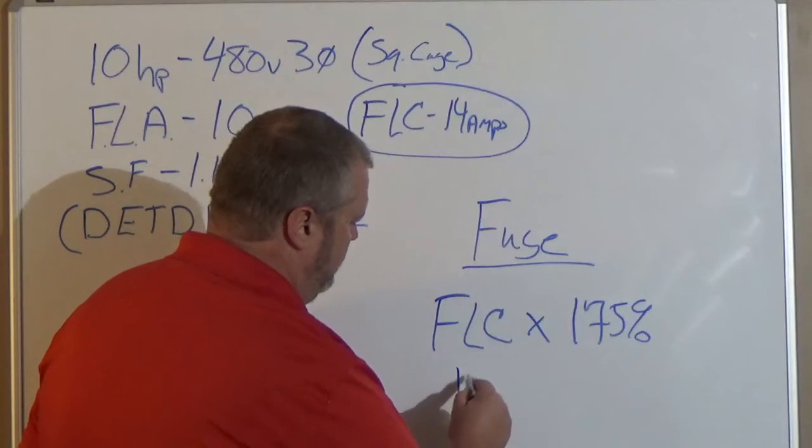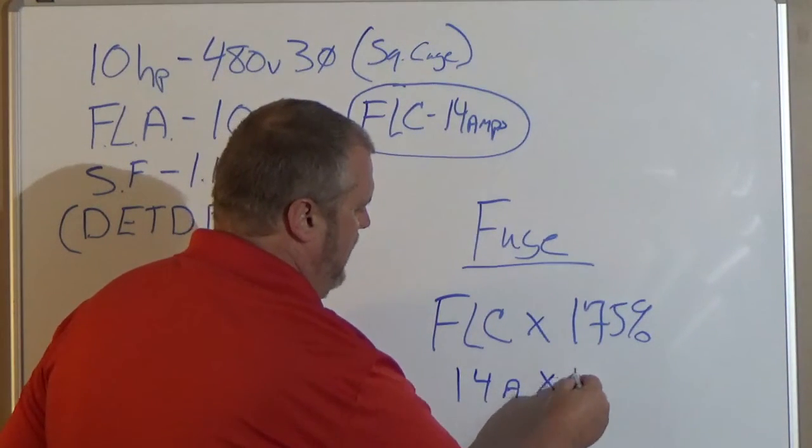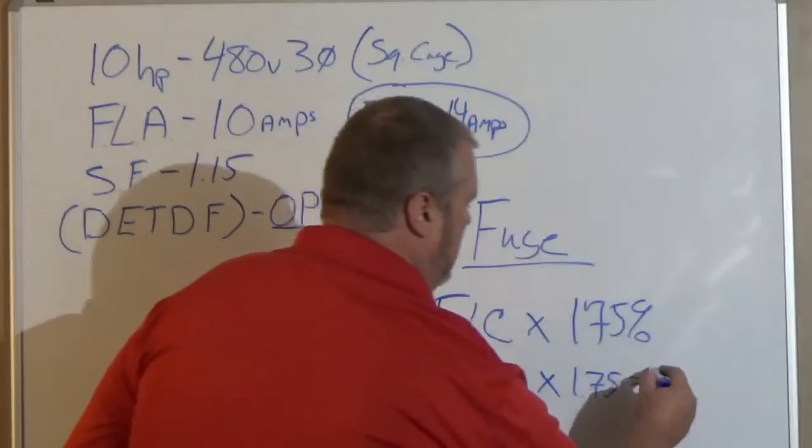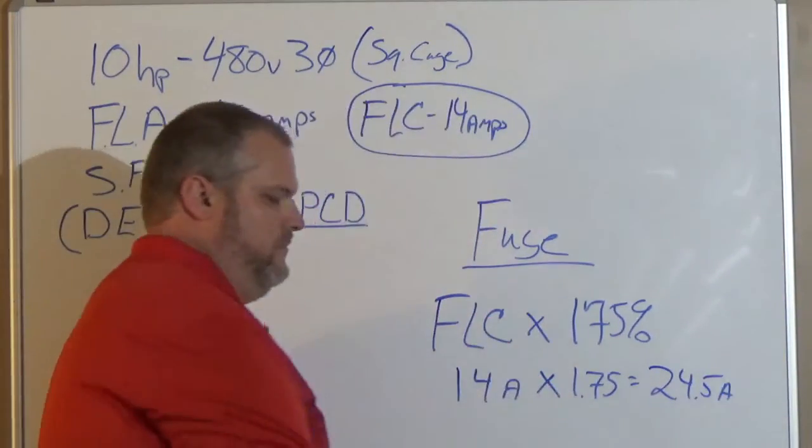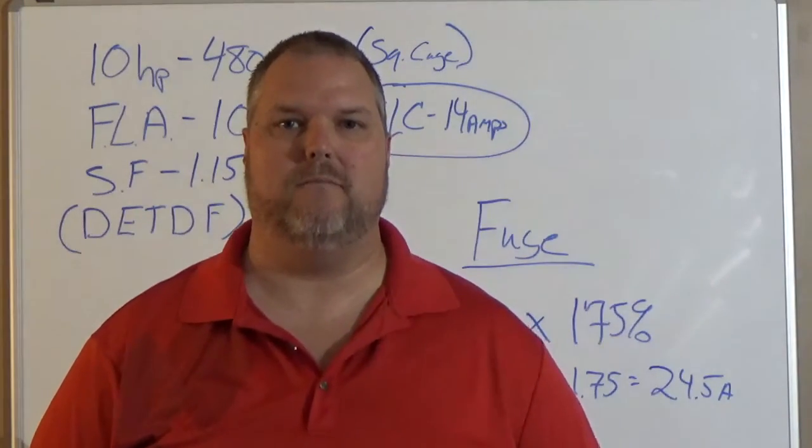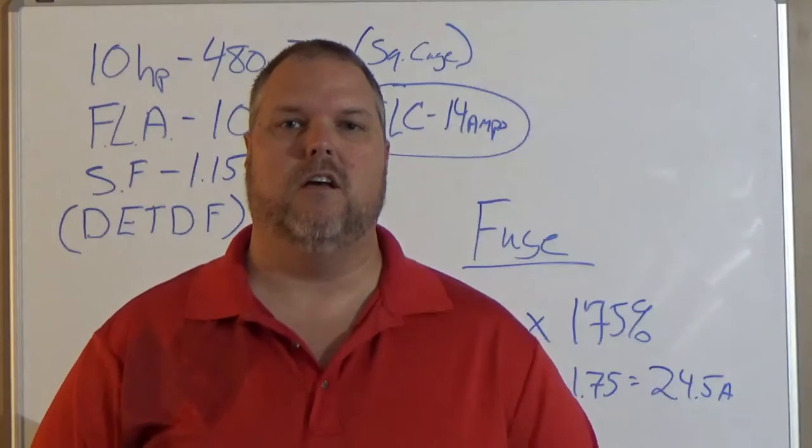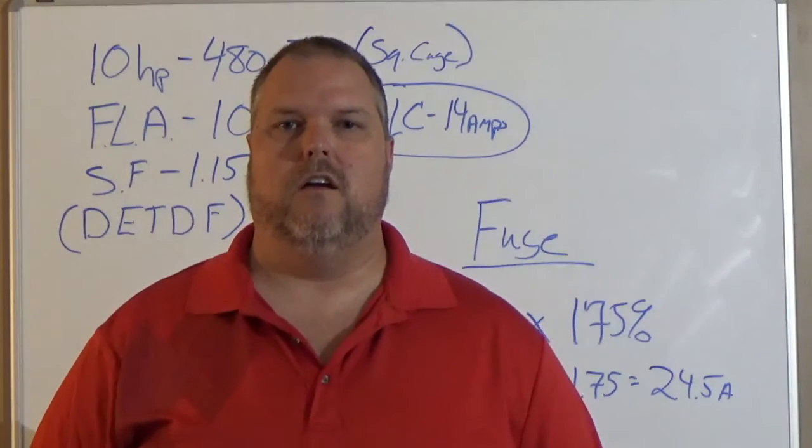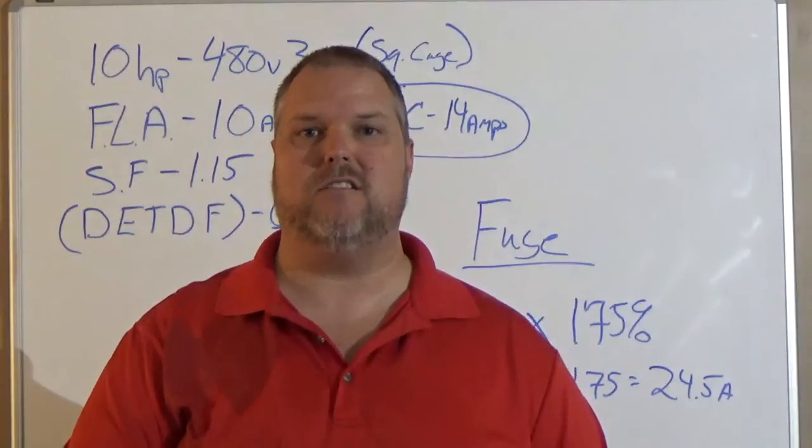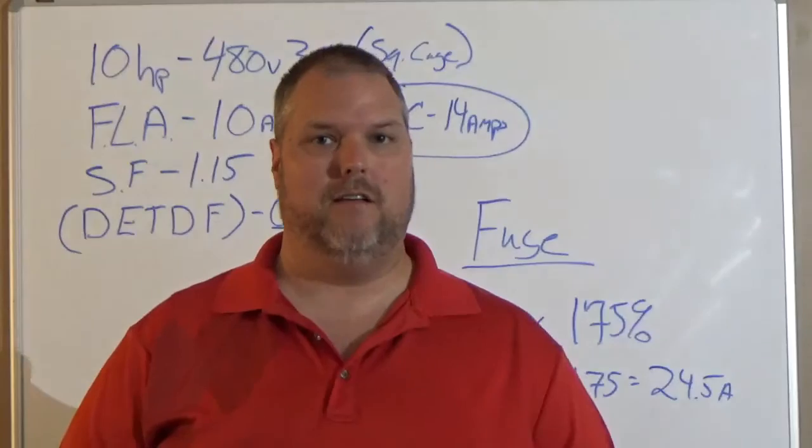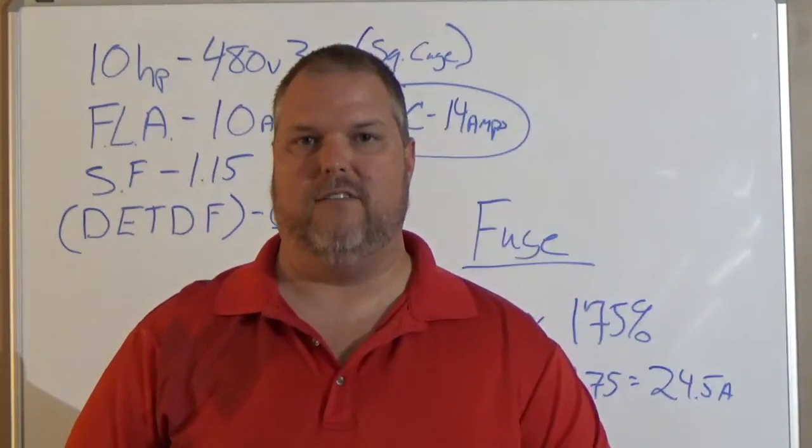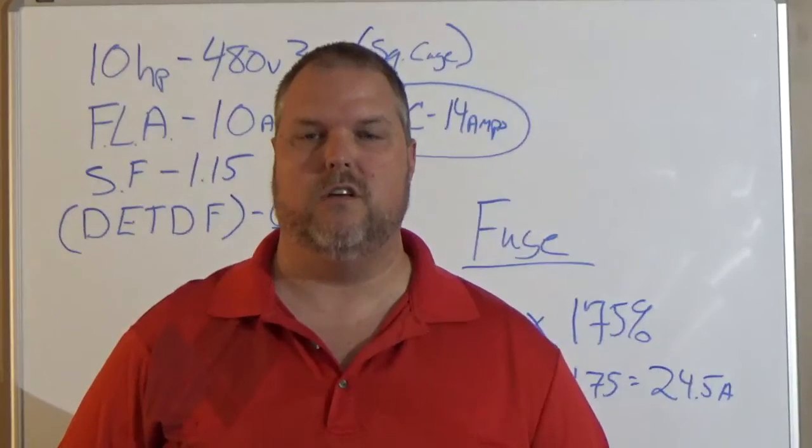Now, they don't make a breaker or a fuse that is 24.5 amps. So what we have to do is we have to go to the next available size. How do you find the next available size? Take yourself over in the code book to article 240.6. It's going to tell you that 25 is our next available size. We don't want to go back to 20 because we're looking at twenty-four and a half amps. That's a lot of amps. So let's just go up one more and let's get a 25 amp fuse. So we're using a dual element time delay fuse that is 25 amps.